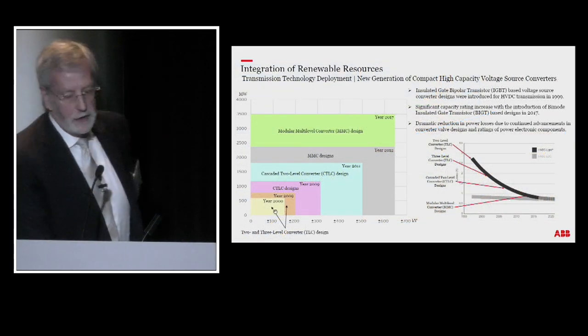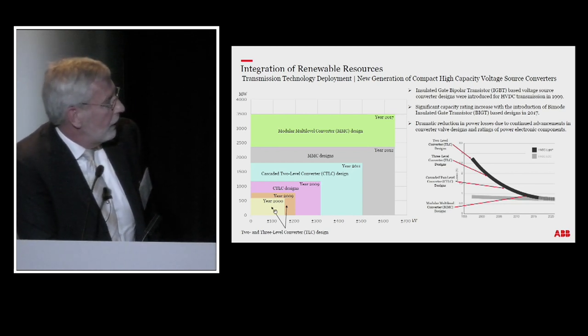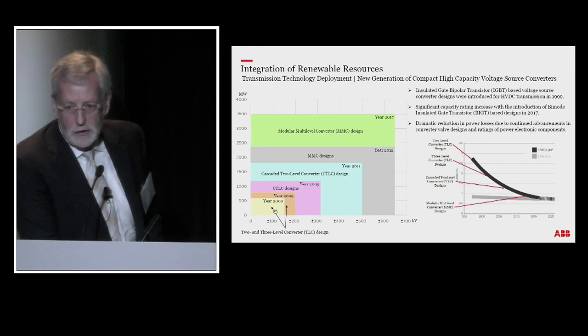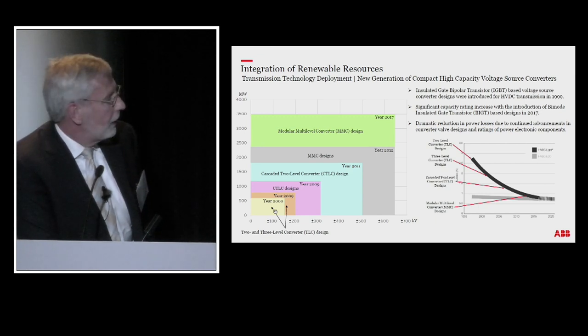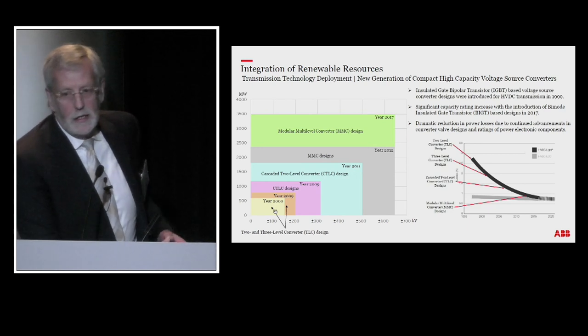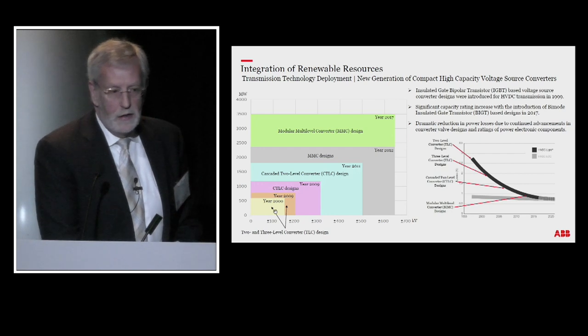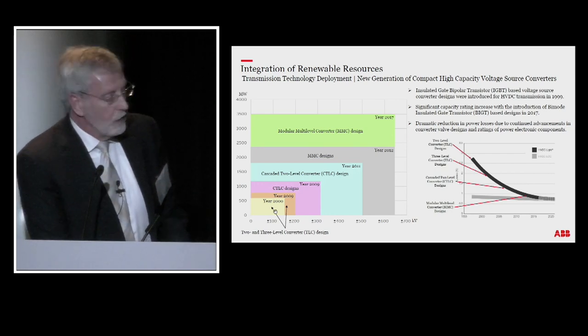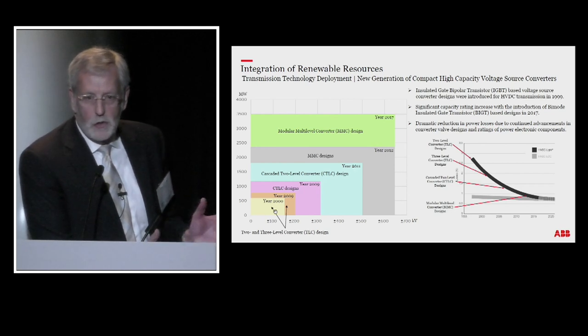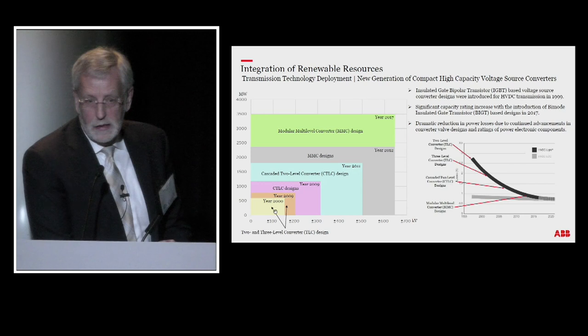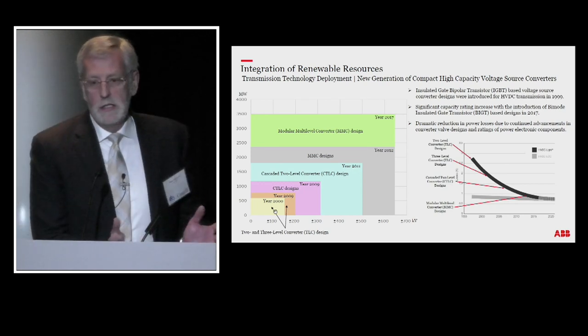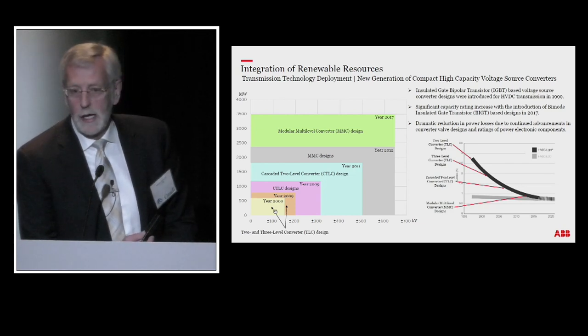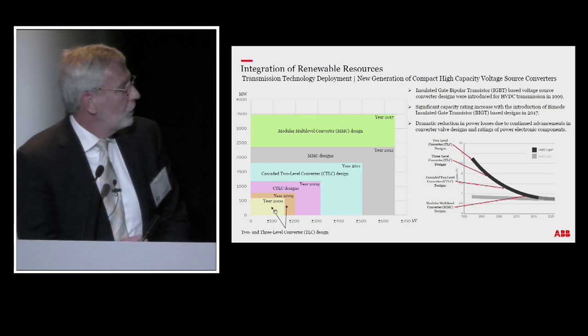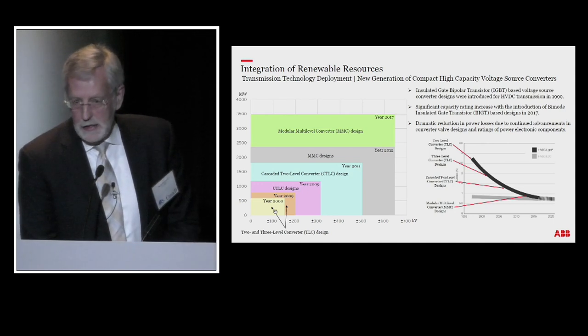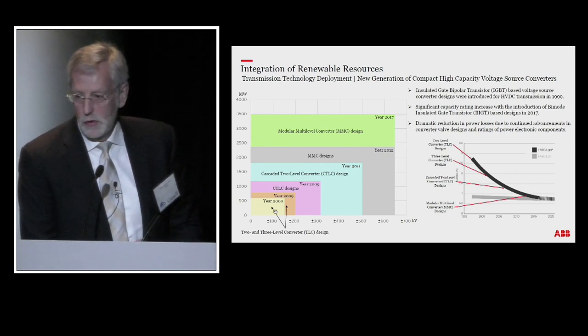In parallel with the development of the cable, there has also been some pretty remarkable development of HVDC converters. What these converters can do is not only supply and deliver real power, but they can also provide reactive power in the same way as a local generator. With continuous development in power electronics and in configurations of DC converters, you now have losses down at 0.6 to 0.7%, and capacity ratings up to 3,500 megawatts.